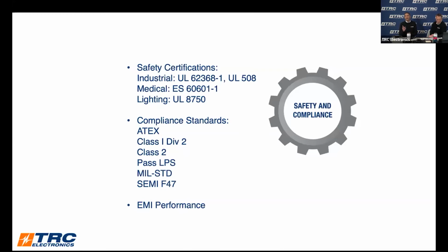The other big one with medical is the monitoring of leakage current and touch current. These are two things that are a must when you're patient connected, to ensure that in a fault condition, should the ground be disconnected, you don't have current flowing through a connected patient and through ground or through a conductive path to ground. So those are very common.